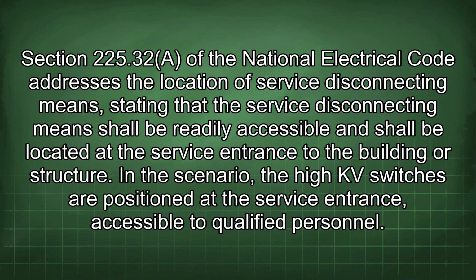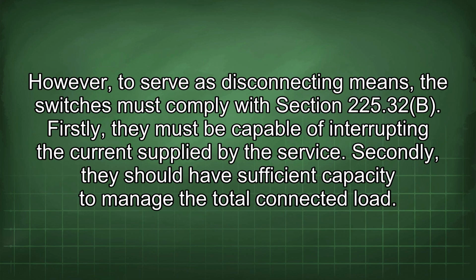Section 225.32 of the National Electrical Code addresses the location of service disconnecting means, stating that the service disconnecting means shall be readily accessible and shall be located at the service entrance to the building or structure. In a scenario, the high kV switches are positioned at the service entrance accessible to qualified personnel.